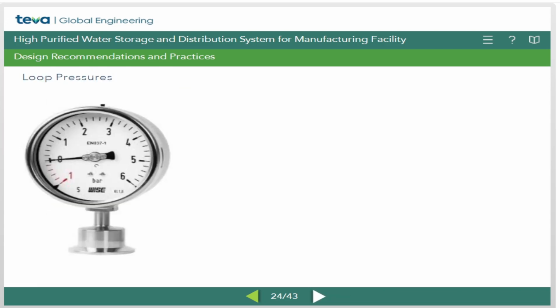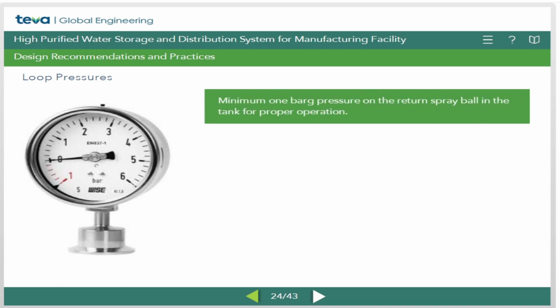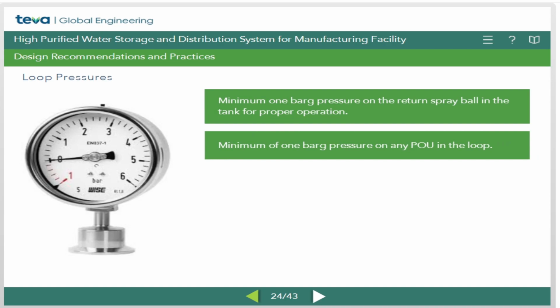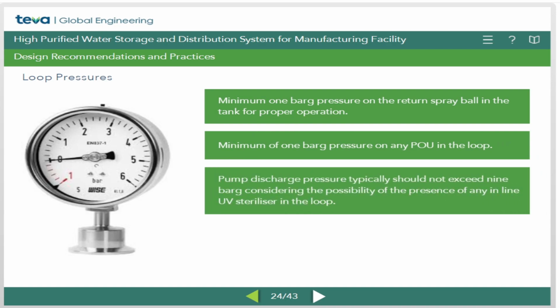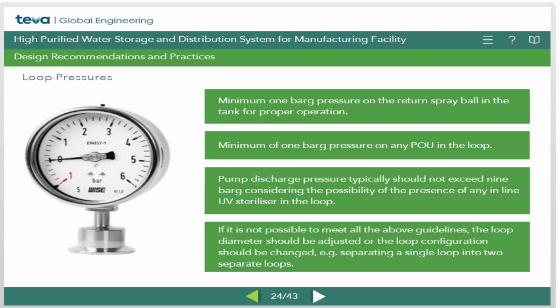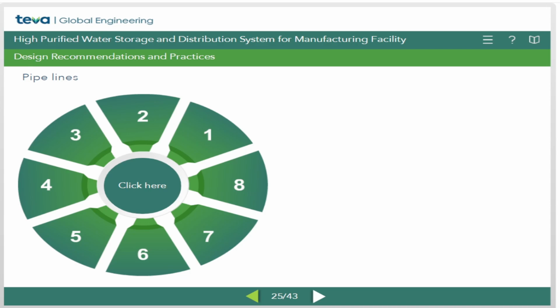The loop pressures must be designed by the following guidelines. Minimum 1 bar G pressure on the return spray ball in the tank for proper operation. Minimum of 1 bar G pressure on any point of use in the loop. Pump discharge pressure typically should not exceed 9 bar G, considering the possibility of the presence of any inline ultraviolet sterilizer in the loop. If it is not possible to meet all the above guidelines, the loop diameter should be adjusted or the loop configuration should be changed. For example, separating a single loop into two separate loops. To learn about pipelines, click on the center button.